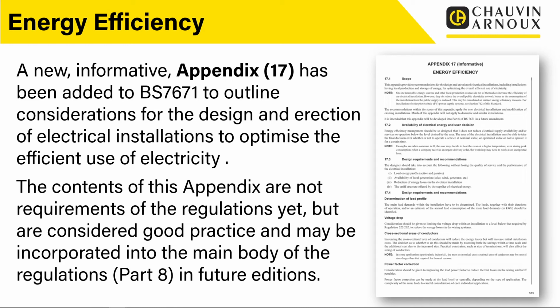However, they actually put a line in there saying that it is intended that this appendix will be developed into Part 8 of BS 7671 in a future amendment. So they are telling us that this is going to get moved into the main body of the regulations, and at that point it's assumed that it will become normative. It will become actually part of the regulations. It won't be informative anymore.